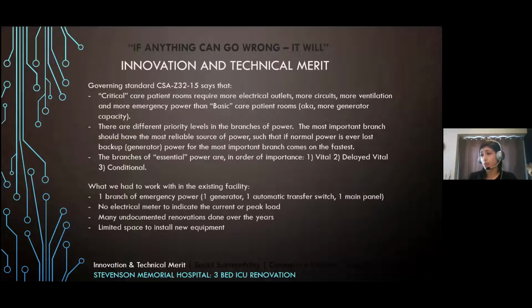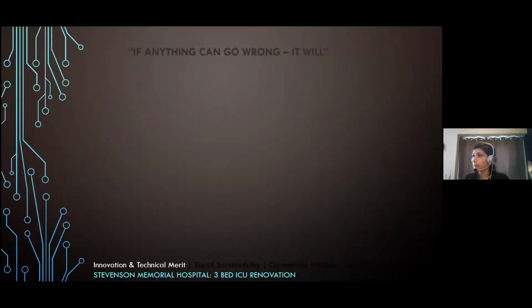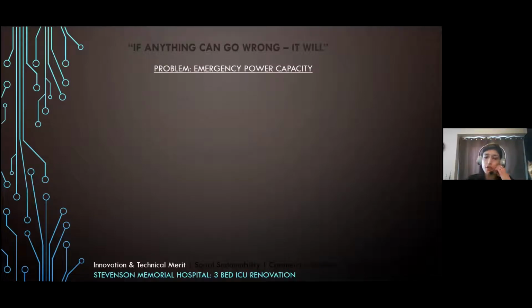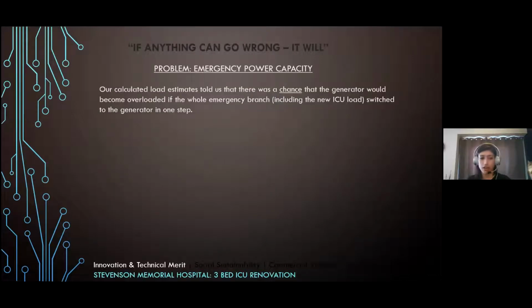In our facility, we had only one branch of emergency power, and there was no electrical meter to indicate the loading on our system. So we realized our biggest problem was not knowing if we had enough capacity on our emergency generator. Because there was no meter anywhere in the system, we had to rely on calculated load estimates, which told us that with our new ICU loads, including all the mechanical equipment, there was a chance that if we lost normal power and switched the entire branch to the generator in one step, we could overload our generator — a scenario we weren't willing to entertain.